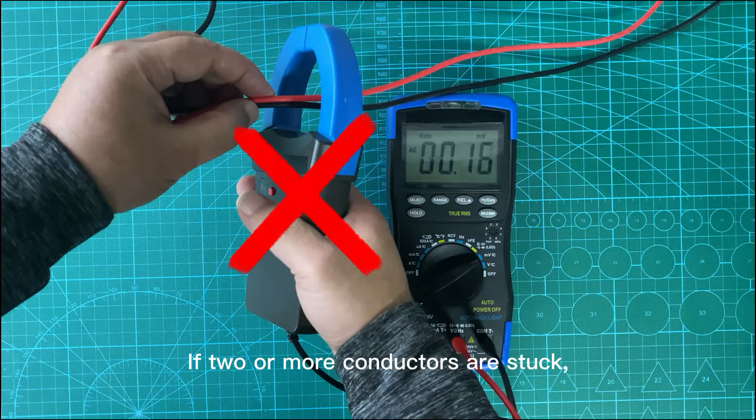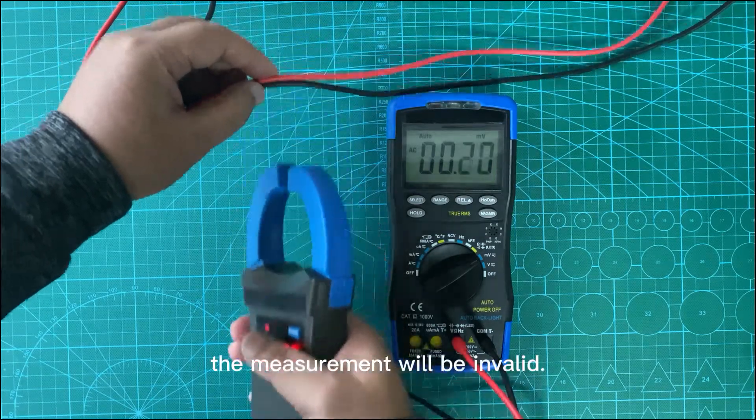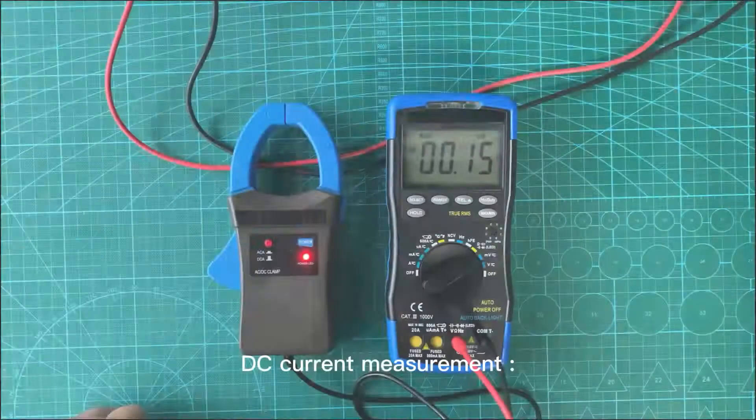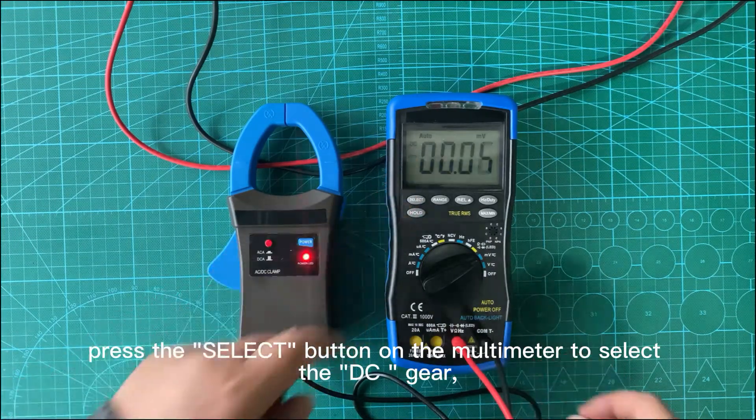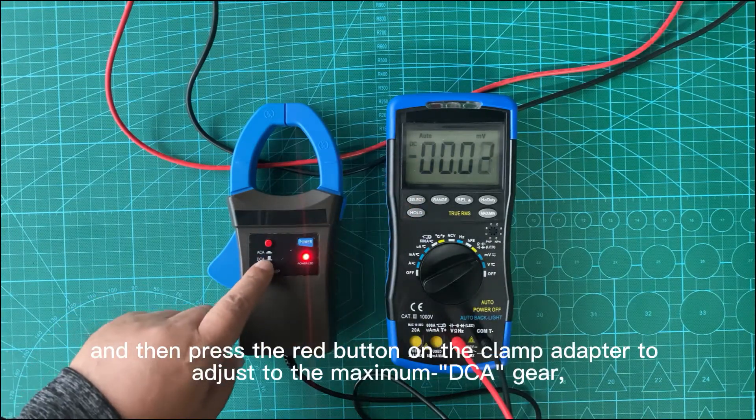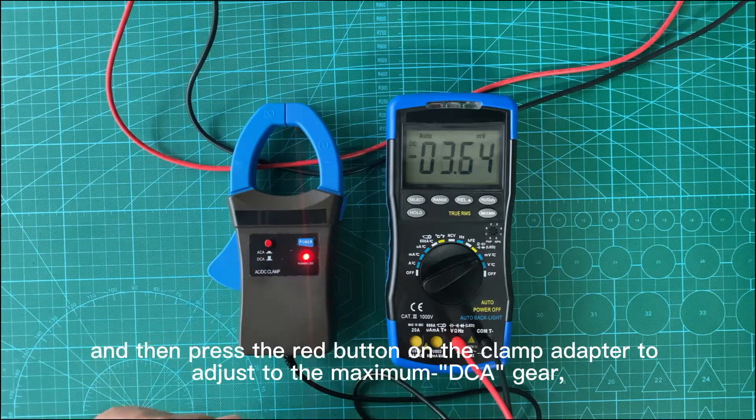If two or more conductors are stuck, the measurement will be invalid. DC current measurement: press the select button on the multimeter to select the DC gear, and then press the red button on the clamp adapter to adjust to the maximum DCA gear.